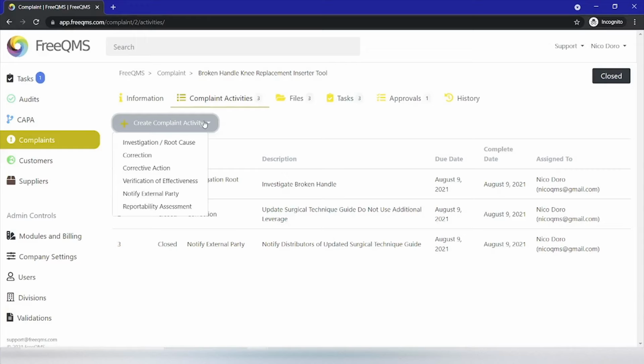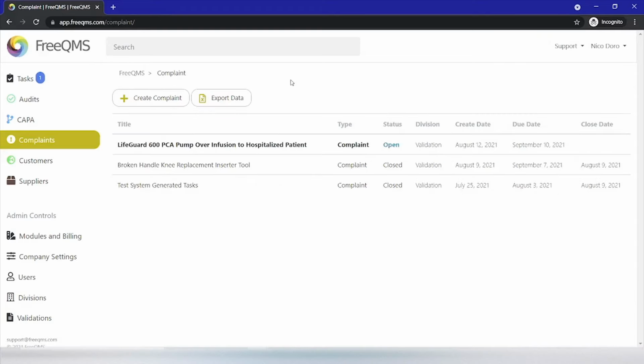In part 4 of this video series, we will complete the verification of effectiveness activity for our complaint, Lifeguard 600 PCA pump over infusion to hospitalized patient, and then close the complaint through a 21 CFR Part 11 compliant electronic signature process under the Approvals tab. As a refresher, we're going to start from the home screen of the Complaints module. We're going to select our complaint, Lifeguard PCA pump over infusion to hospitalized patient.